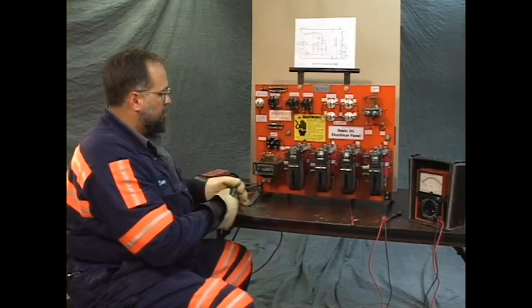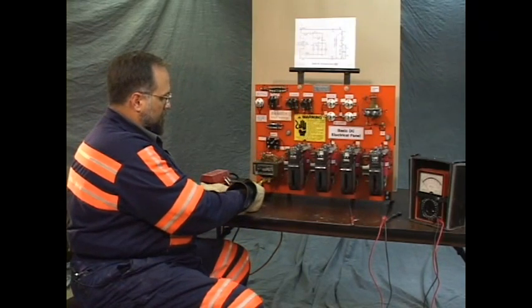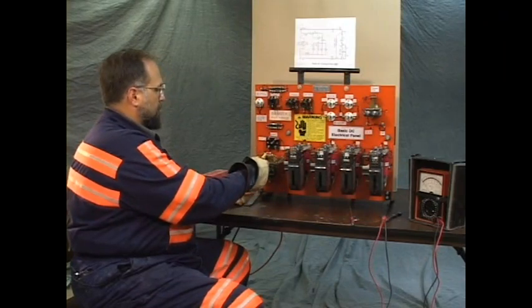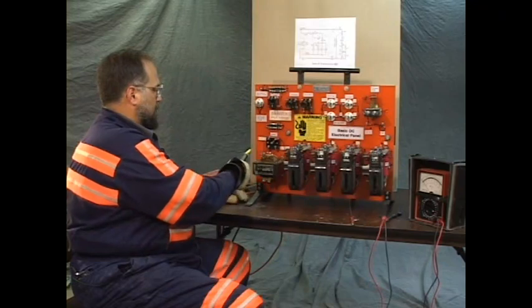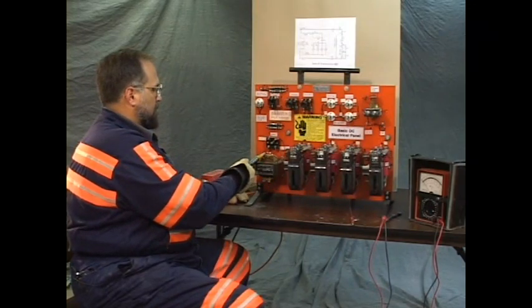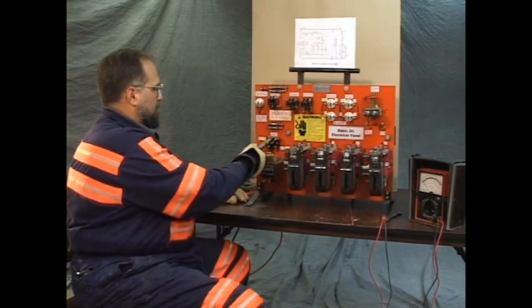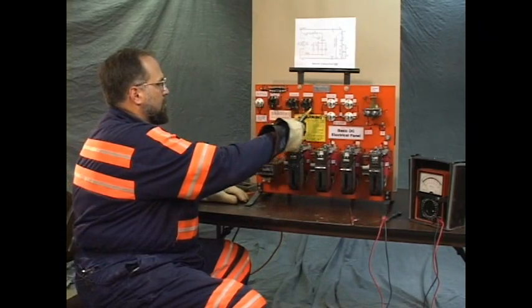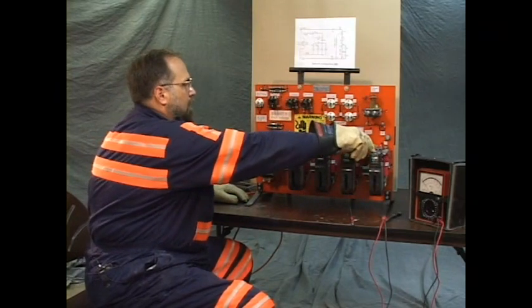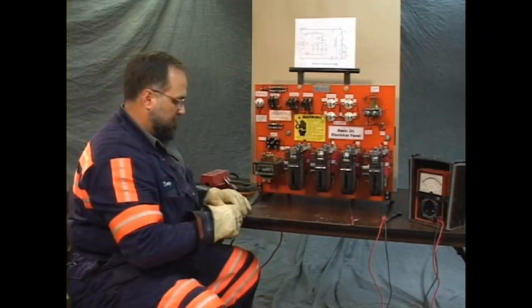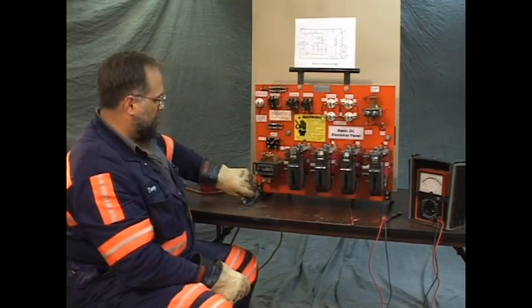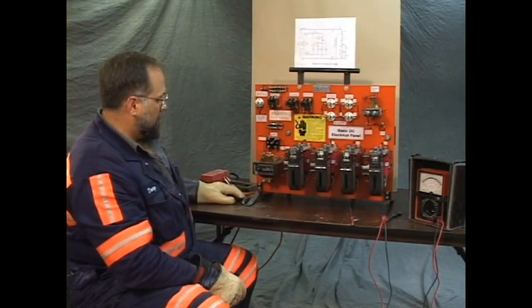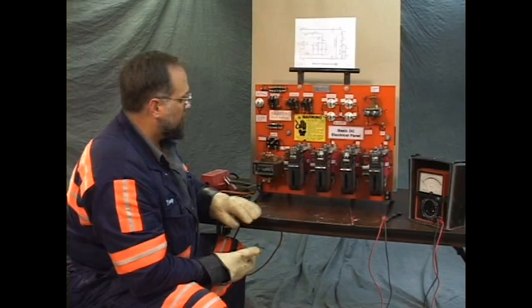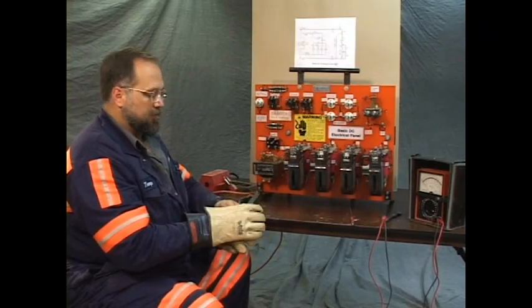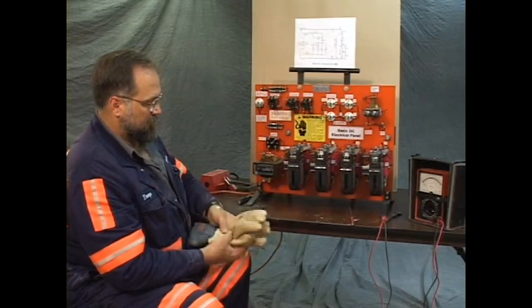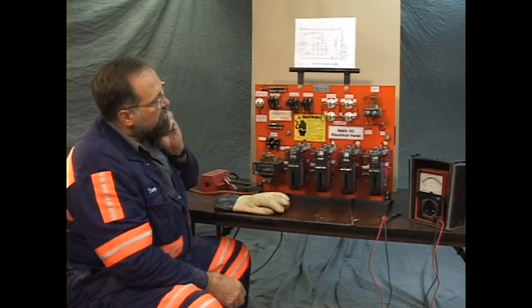Now we're going to take our voltage detector and see if we can find some power. And we don't have any. All is well. You have the occasional chirp from the instrument there from moving it too rapidly. But when you encounter an energized circuit, it alarms with a solid alarm. It's safe to take the gloves off now to troubleshoot this.